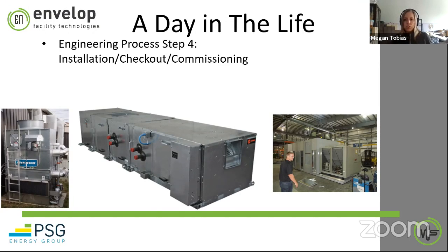At my company, controls engineers also assist with this process when needed, especially with what we call commissioning. We go out in the field once the system's been started up and run each program and system through its paces to make sure it's working as intended, making tweaks as necessary, because it might work in theory when you're sitting in the office, but in practice there's typically always some tweaks that need to be made. That's part of the fun of it.